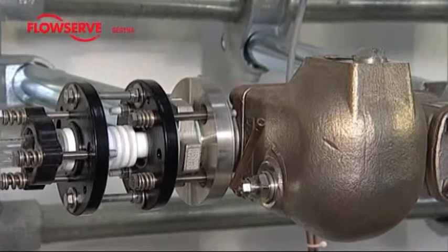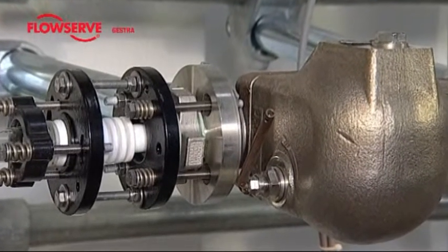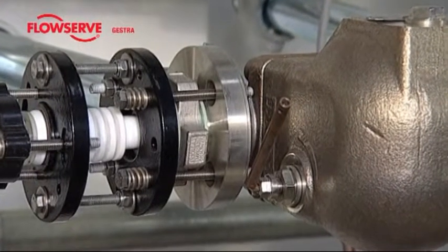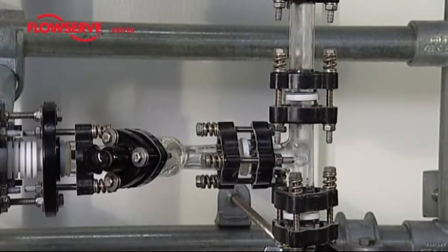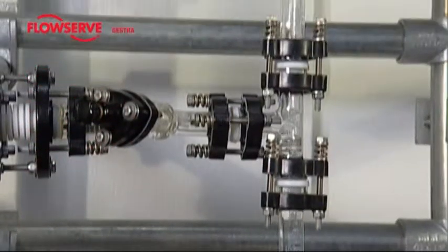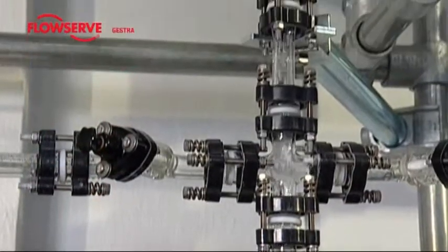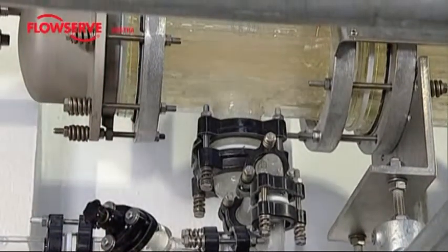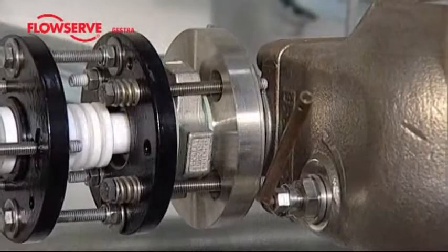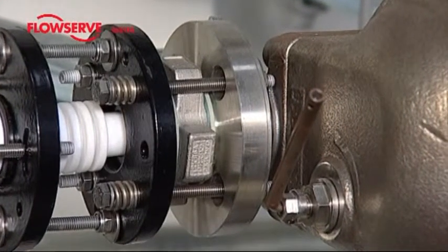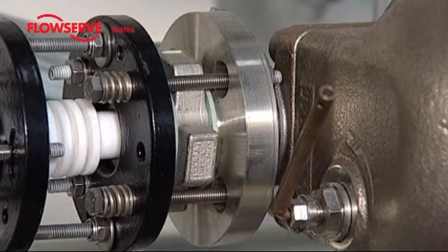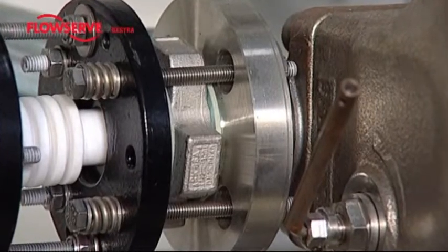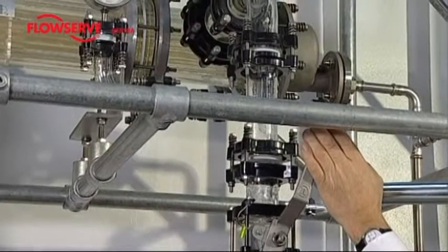For certain installations, it's advisable to provide a non-return valve downstream of the float trap. If it's possible that the back pressure is higher than the upstream pressure, this prevents a reflux of condensate. When the steam control valve at the input of the heat exchanger closes, this can result in an extremely rapid pressure drop. A vacuum may be produced inside the heat exchanger. Condensate is then drawn through the steam trap back into the heat exchanger. This too is prevented by a non-return valve. In both of these cases, the Gestra Disco non-return valve type RK has proven to be most effective.